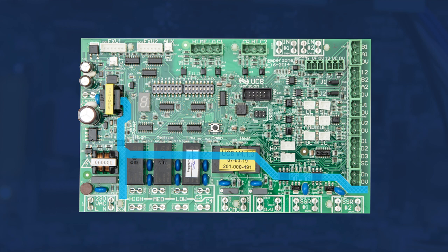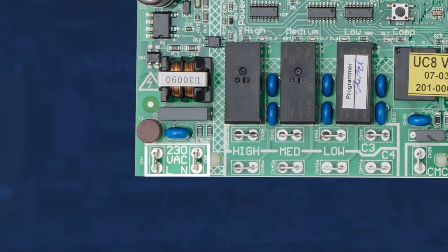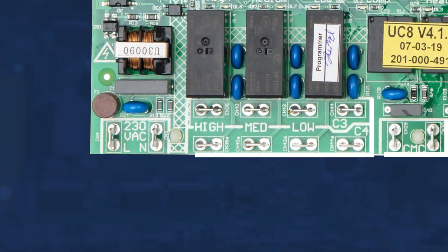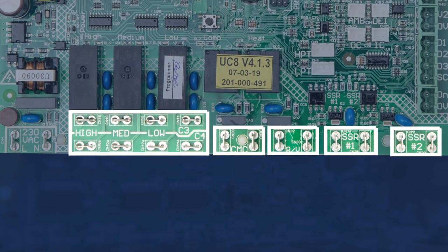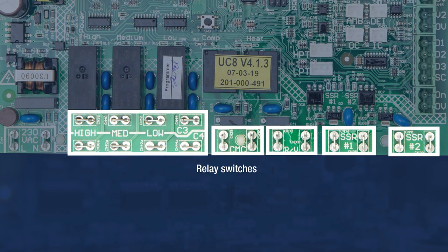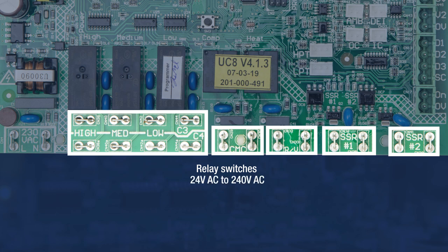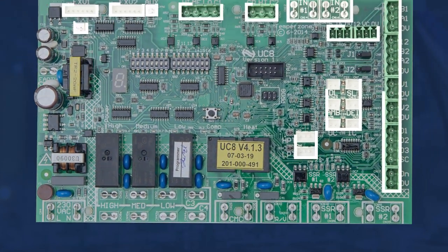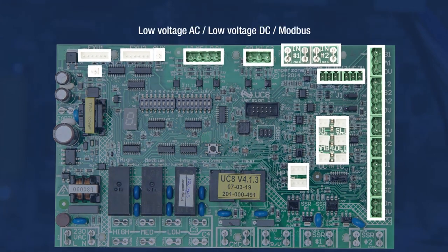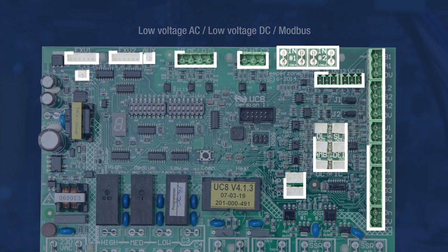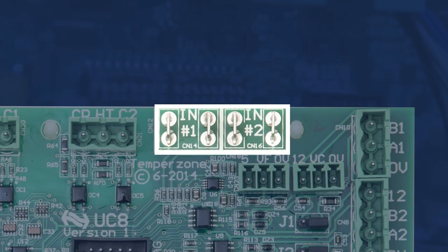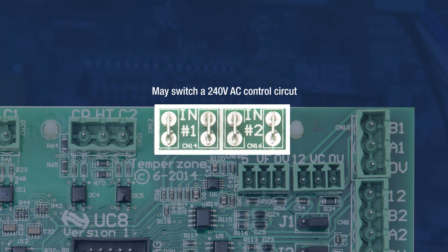Terminals to the left of the vertical line up to the earth spade are the 240 volt AC power input. All terminals below the diagonal lines are relay switches and may contain 240 volt AC or 24 volt AC. All terminals outside of this region are low voltage AC, low voltage DC, and Modbus, with the exception of IN1 and IN2, which sometimes may switch a 240 volt AC control circuit.